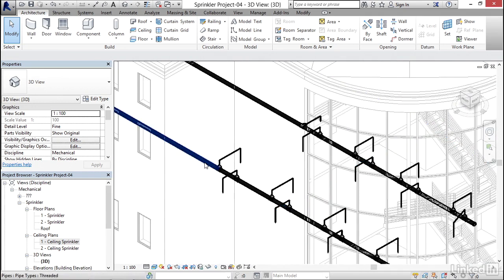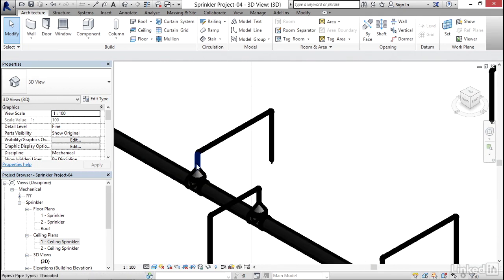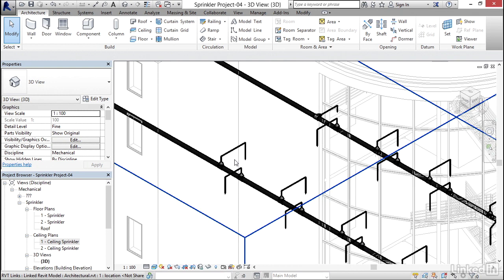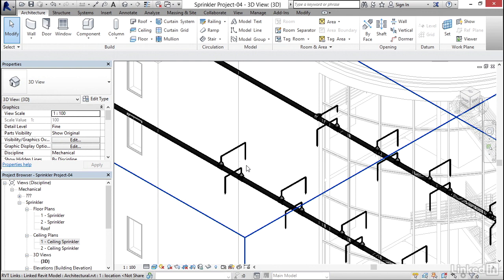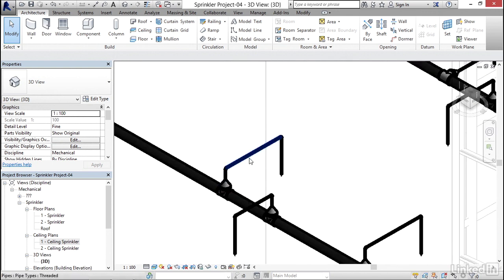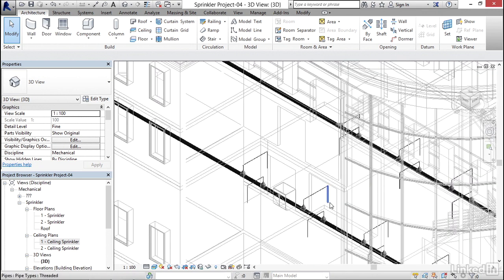Now if we need to make any adjustment to our mains, we have a little bit of wiggle room in here. But of course, always cut a section and make sure you know what you've got between the deck, the bottom of the steel, and the top of the ceiling. Also, make sure you have other trades turned on in your model. You might not have that clean of a shot. It's going to be easier for you to move your branch piping than it is for someone to move a giant piece of ductwork.